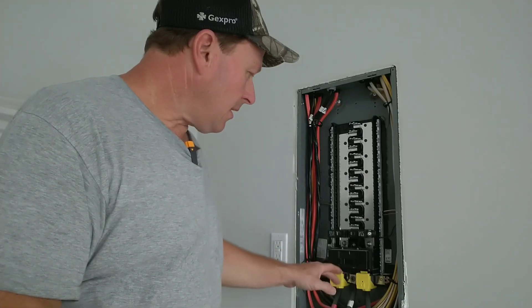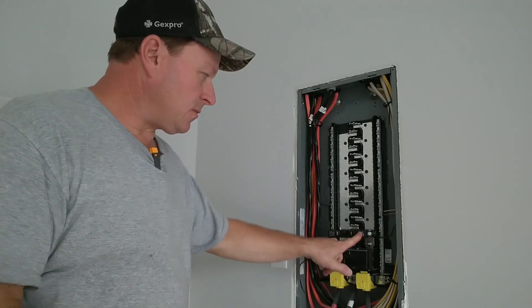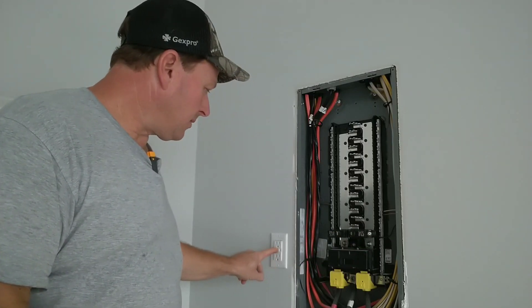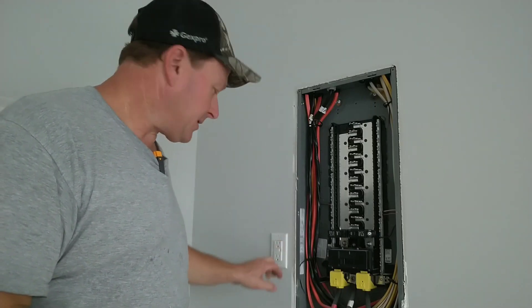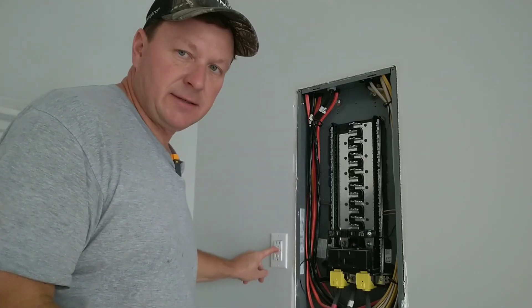I'm going to have to make an extra trip, go get a brand new 200-amp main breaker, and swap this out when they come back. Originally I found out there was a problem when I turned the main on, turned the 120-volt breaker on, and went to reset the GFI — because usually brand new these things are tripped right out of the package, and the light will glow and you reset it to initiate power.